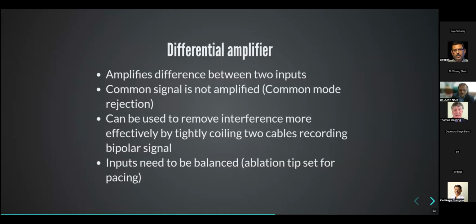As I discussed, the amplifier works on a principle of differential amplification, where it amplifies the difference between two inputs. One of the things this means is that the noise level should be the same on the two inputs. If you're recording a bipolar, both of them should be recording similar signals so that the noise can be balanced and removed. So usually the connecting cable that comes from a bipolar has tightly coiled cables, which allows balancing of these two inputs. This is also why, if you start pacing from the ablation tip, you'll start getting a lot of noise on the ablation, because the one electrode that you opened for pacing makes them unbalanced and introduces noise. As soon as you finish pacing, you have to disable pacing on that, so that the noise will be reduced.